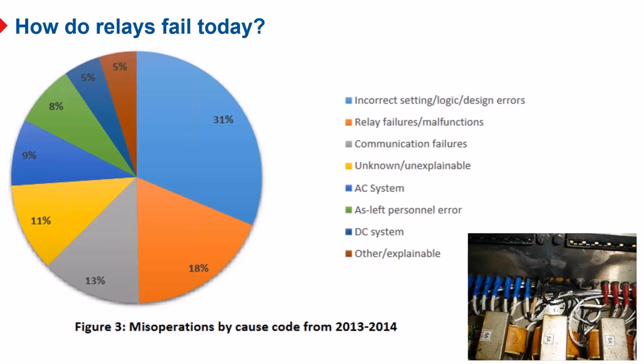Utilities now have to report those misoperations above 100 kV, hence this misoperation report that NERC publishes every couple of years. I know this data is a little bit old, but the percentages haven't really changed that much. This is a pie chart showing the misoperations of protection systems by cause about 10 years ago, 2013, 2014. For those of you that are in the business, this really shouldn't come as much surprise. A full third of the reportable relay misoperations were due to incorrect settings, logic, and design errors. Then 18% are actually relay failures and malfunctions, 13% communication failures, and you can read the rest of the pie chart.